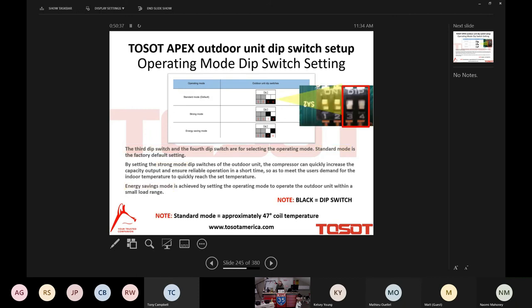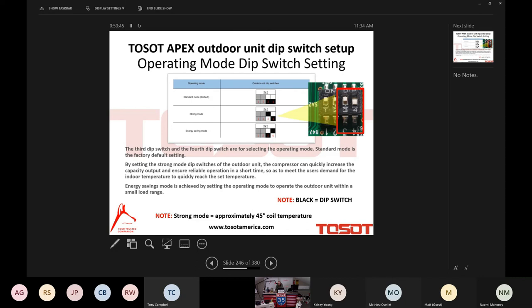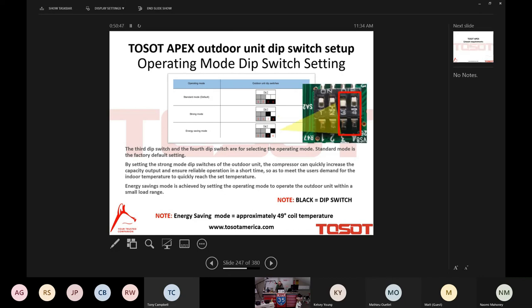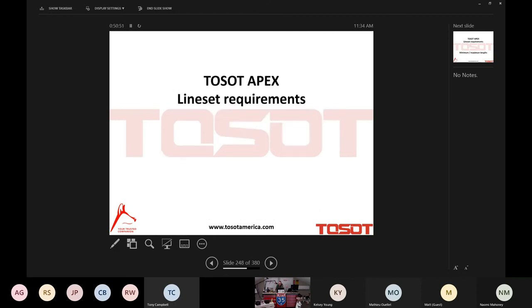And there you can see the dip switch settings for 3 and 4 for the standard mode. You can see they're both down. For the strong mode, 3 is up, 4 is down. And for the energy savings mode, 3 is down, 4 is up. Beautiful. Line set requirements. We're in the home stretch, guys. I promise. And I still got a half an hour with you, so we're good.